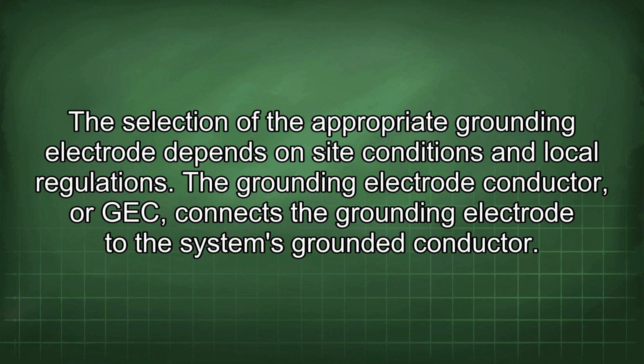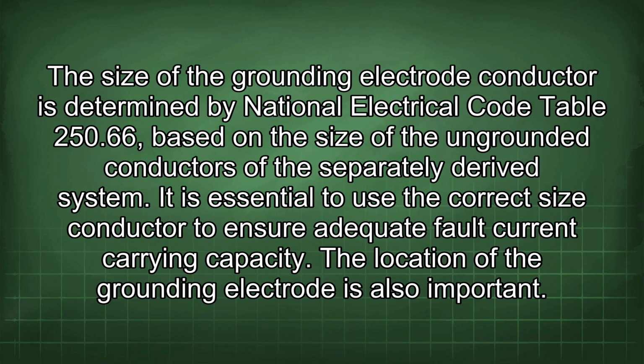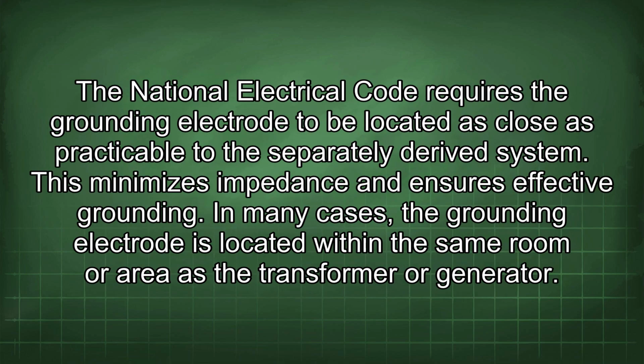The grounding electrode conductor, or GEC, connects the grounding electrode to the system's grounded conductor. The size of the grounding electrode conductor is determined by National Electrical Code Table 250.66, based on the size of the ungrounded conductors of the separately derived system. It is essential to use the correct size conductor to ensure adequate fault current carrying capacity. The location of the grounding electrode is also important. The National Electrical Code requires the grounding electrode to be located as close as practicable to the separately derived system. This minimizes impedance and ensures effective grounding. In many cases, the grounding electrode is located within the same room or area as the transformer or generator.